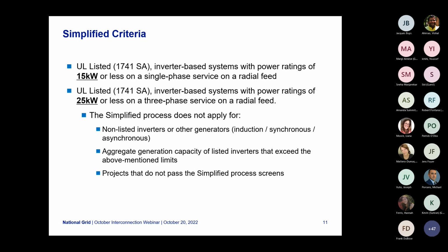It is a UL listed 1741SA at the moment, which will be converted in the future to 1741SB, for inverter-based systems with power ratings of 15 kW or less on a single phase service on a radial feed, or UL listed inverter-based systems with power ratings of 25 kW or less on a three-phase service on a radial feed.